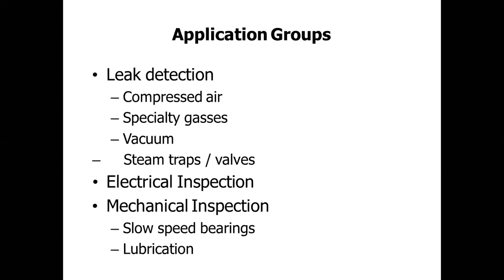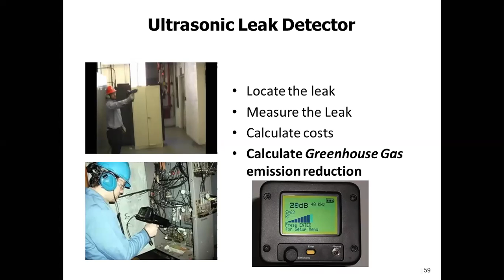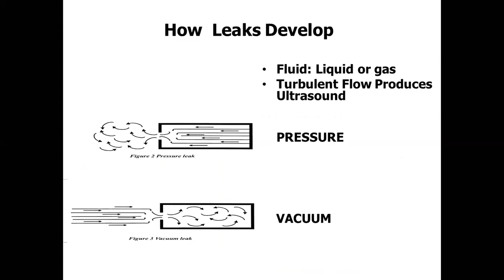Then ultrasound leak detectors, which locate the leak in a machine or in a component. It also measures the leak, calculates the cost, and calculates the greenhouse gas emission reduction. So this is all about the ultrasonic leak detector. Now how do leaks develop? It may be fluid, liquid or gases. For example, because of pressure and because of vacuum, the leak is developed. That leak can be detected by an ultrasonic leak detector machine.